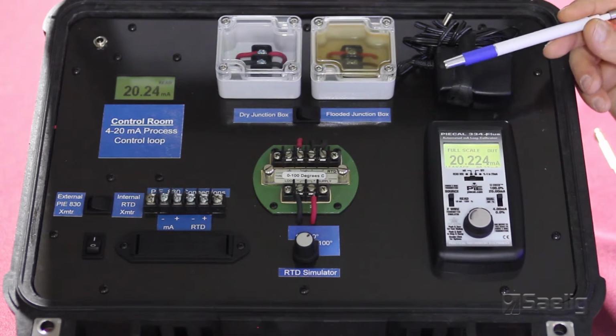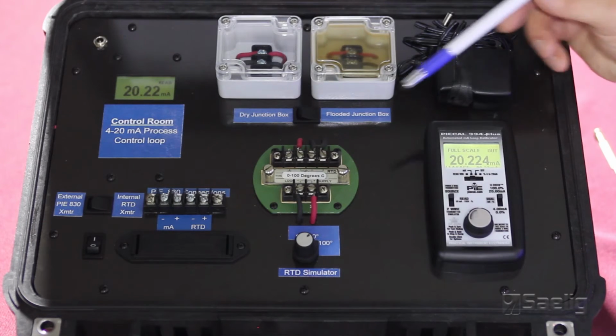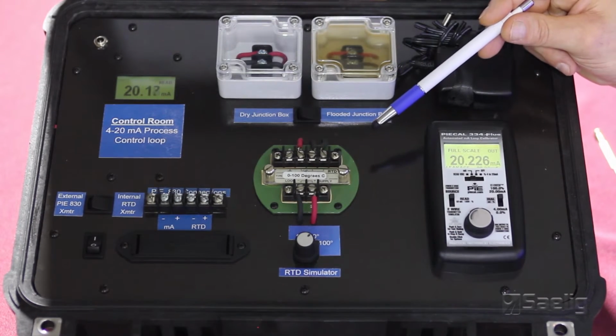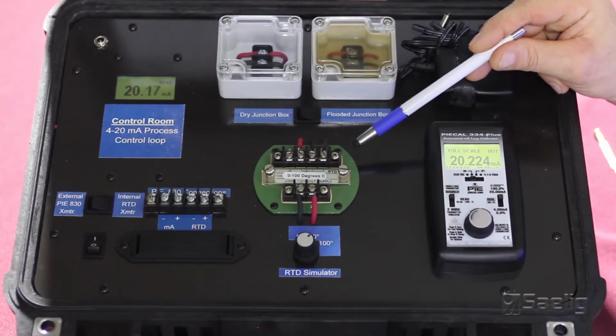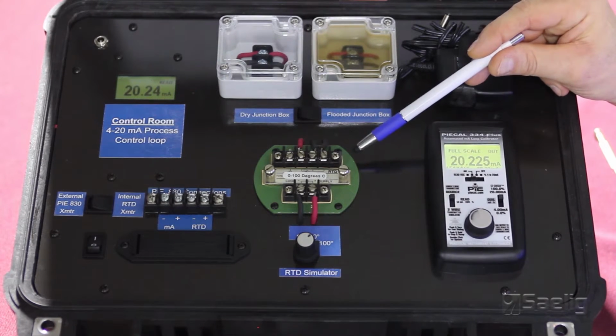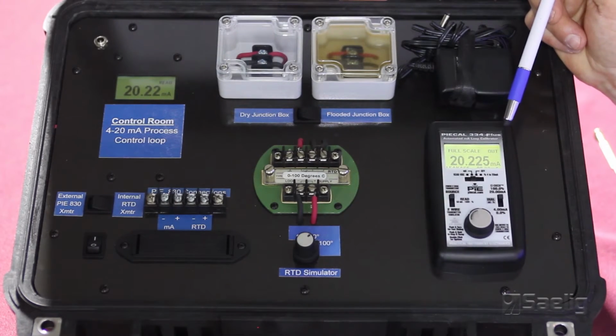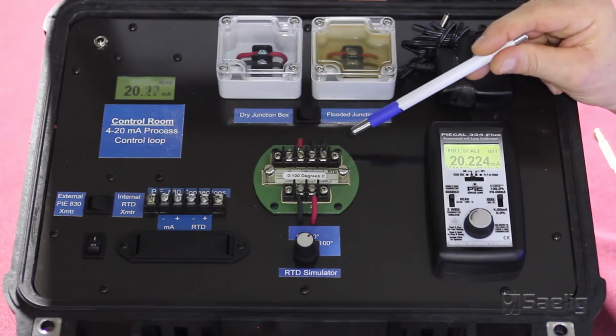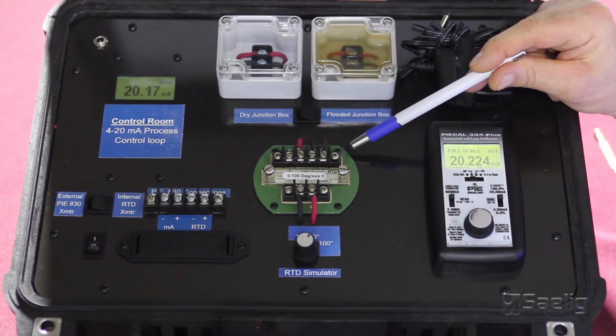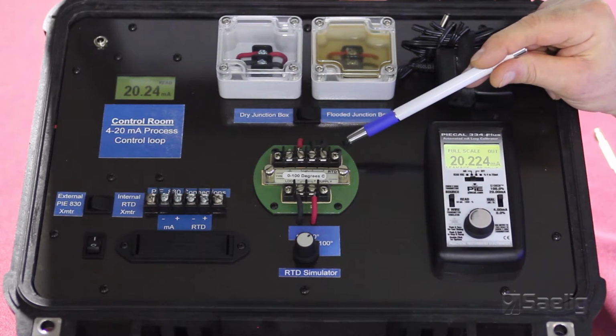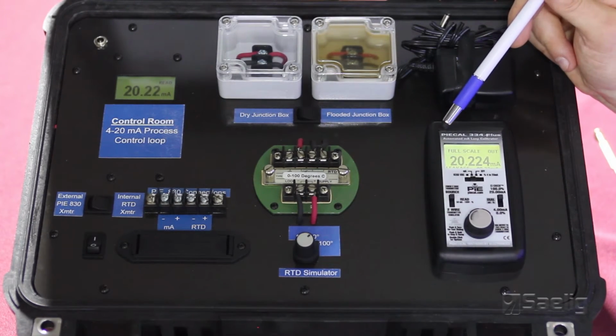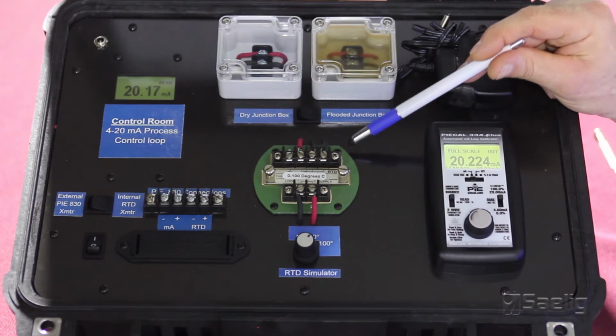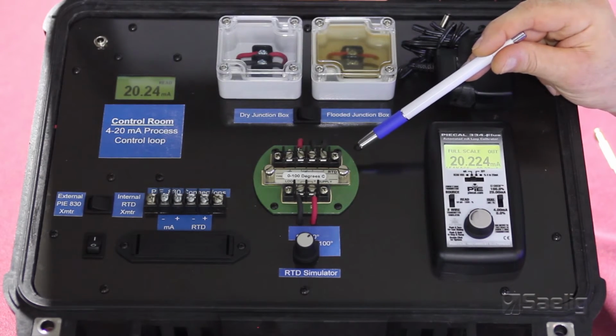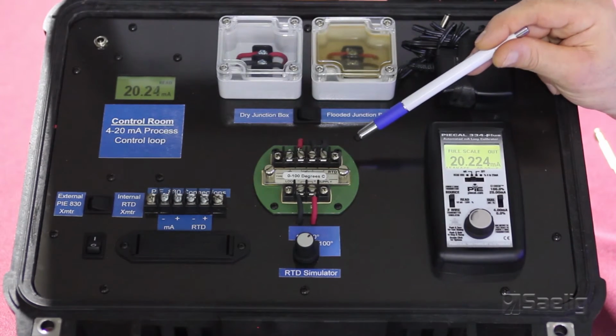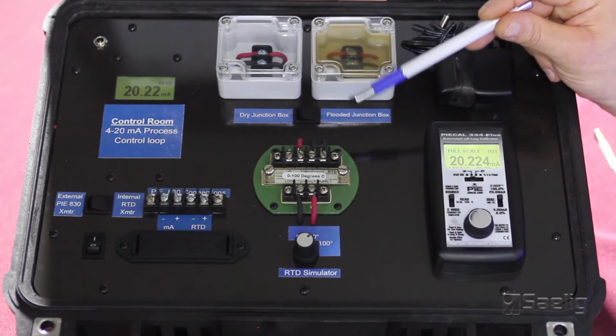The problem with leakage current in a loop is that it's bypassing your transmitter. So if you go and replace the transmitter and put a new one in, there will still be a problem with leakage current. The other option, which is done in error, will be to try to adjust the transmitter to take the output of it down to 20 milliamps. The difficulty and the danger there is now we've adjusted a loop incorrectly because there's a problem with moisture condensation in the loop wiring.